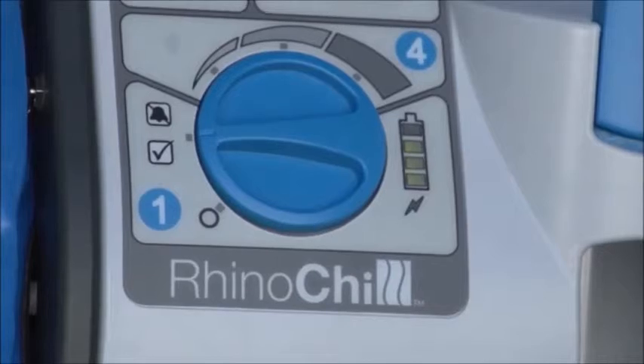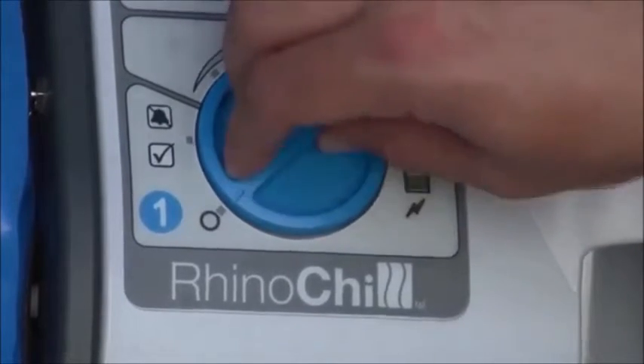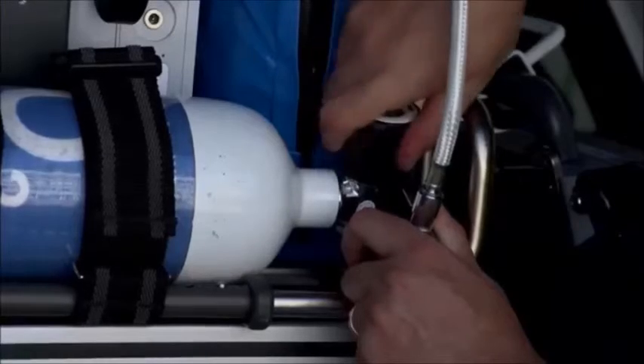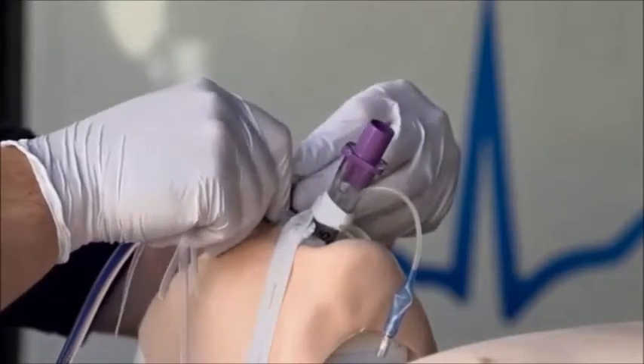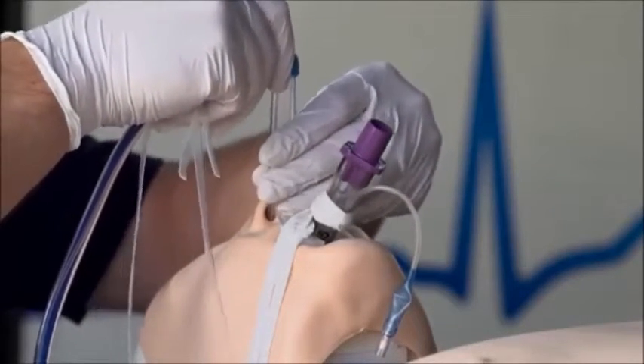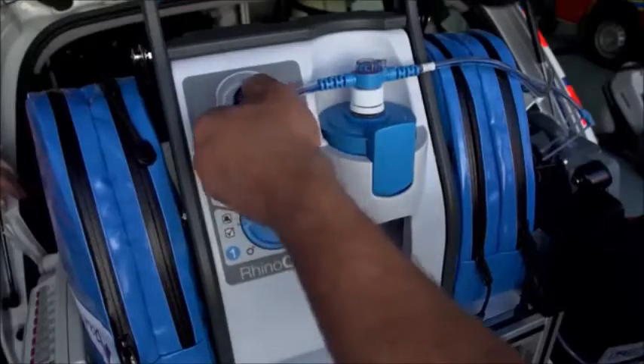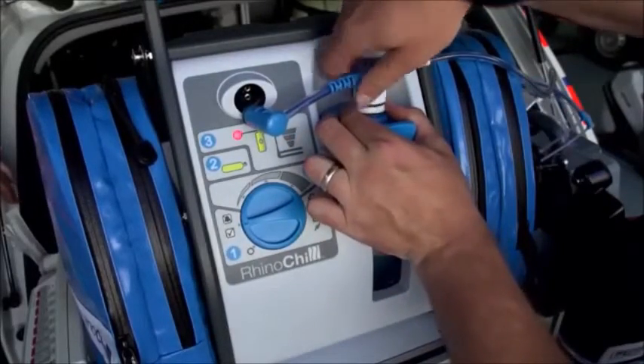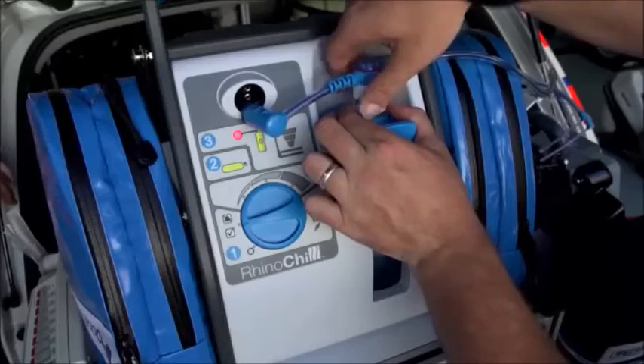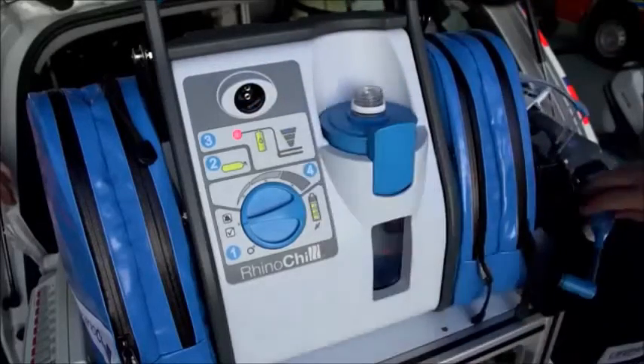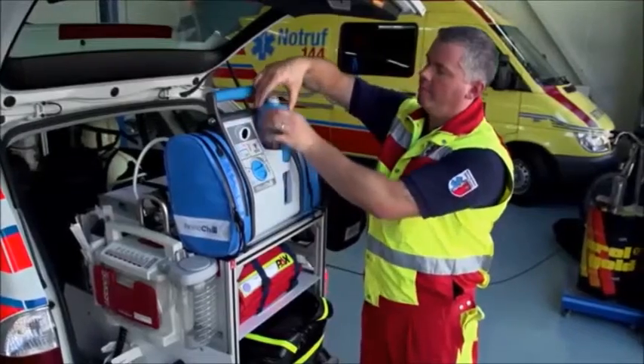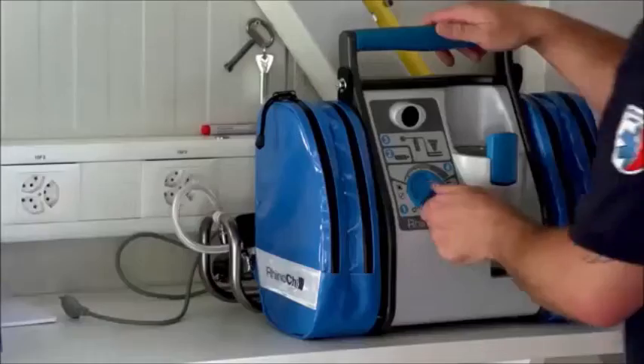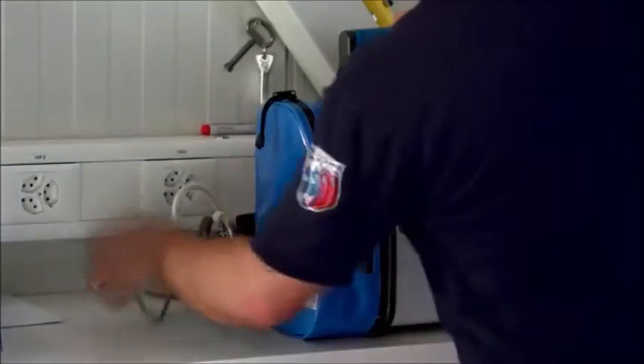Once the decision has been made to stop cooling with the Rhinochill, turn the control knob setting to the off position. Close the gas supply valve and then remove the nasal cannula from the patient's nose. The cooling catheter assembly can then be disconnected from the control unit and the coolant bottle and can be disposed of as per local biohazardous waste guidelines. The coolant bottle can then be removed and the cap replaced.